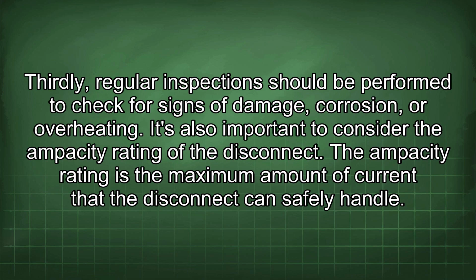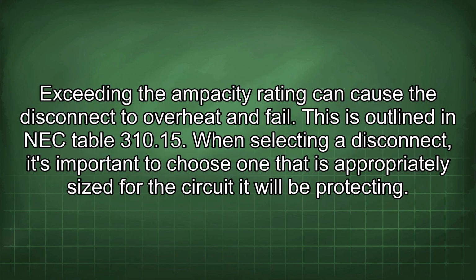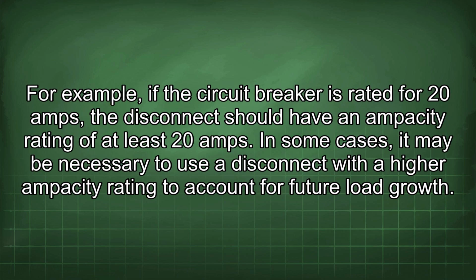It's also important to consider the ampacity rating of the disconnect. The ampacity rating is the maximum amount of current a disconnect can safely handle. Exceeding the ampacity rating can cause the disconnect to overheat and fail. This is outlined in NEC Table 310.15. When selecting a disconnect, it's important to choose one that is appropriately sized for the circuit it will be protecting. For example, if the circuit breaker is rated for 20 amps, the disconnect should have an ampacity rating of at least 20 amps. In some cases, it may be necessary to use a disconnect with a higher ampacity rating to account for future load growth.